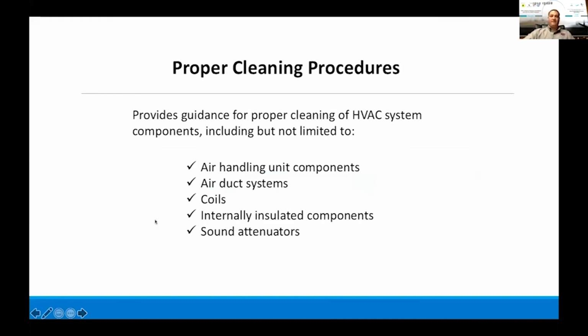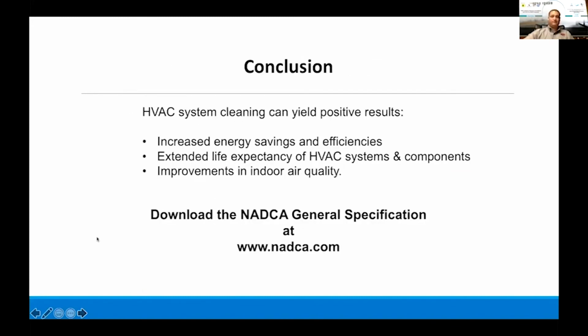The standard provides guidance for proper cleaning of HVAC system components, including but not limited to air handling units, air duct systems, coils, internally insulated components, and sound attenuators. There are more components than this that the ACR addresses to be cleaned within the standard. HVAC system cleaning can yield positive results: increased energy savings and efficiencies, which are measurable items, extended life expectancy of HVAC systems and components, and improvements in indoor air quality. Again, there's the download at NADCA.com to be able to get a free copy.